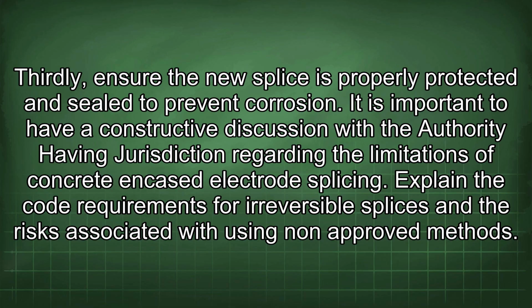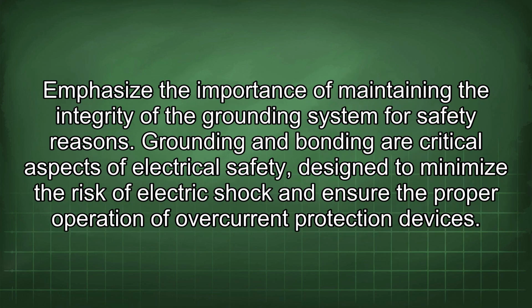It is important to have a constructive discussion with the authority having jurisdiction regarding the limitations of concrete encased electrode splicing. Explain the code requirements for irreversible splices and the risks associated with using non-approved methods. Emphasize the importance of maintaining the integrity of the grounding system for safety reasons. Grounding and bonding are critical aspects of electrical safety, designed to minimize the risk of electric shock and ensure the proper operation of overcurrent protection devices.